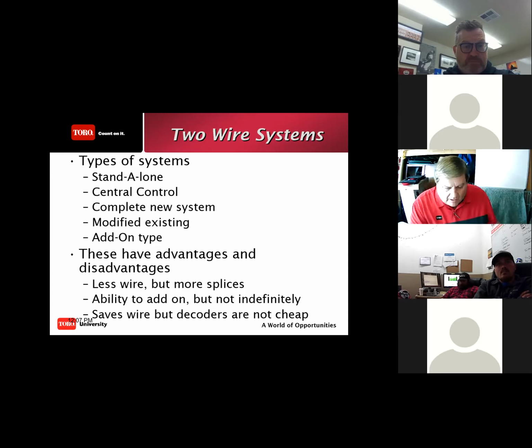But you have a two-wire line in this system that feeds everything. So where the line gets cut, everything up to that point works, and after that doesn't work anymore. You can add on to it, but not indefinitely. And that becomes a very brand specific adding onto the system, how many you can add on. So the savings comes from much less wire, but now you're having little miniature controllers located out in the field. They're not cheap. Now you have a lot more wire connections, and we'll get into that in just a moment.